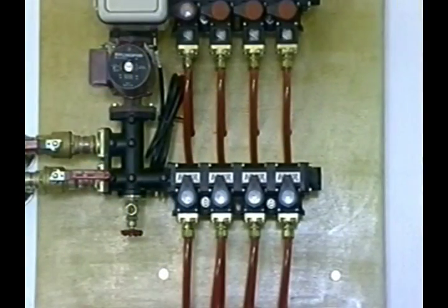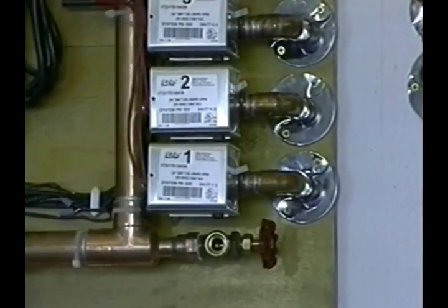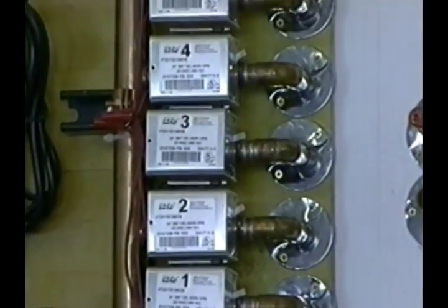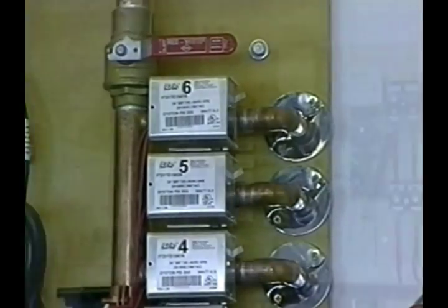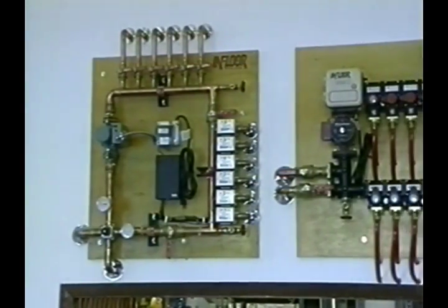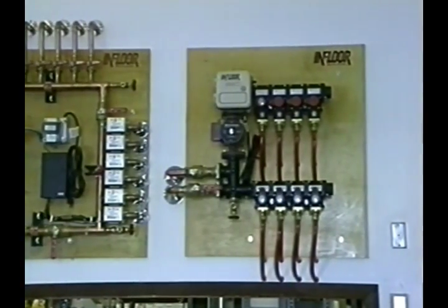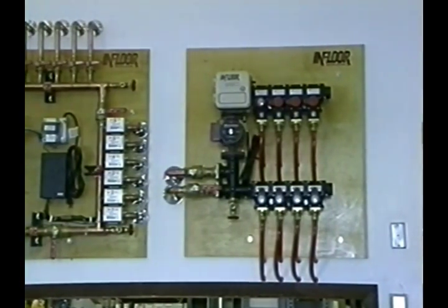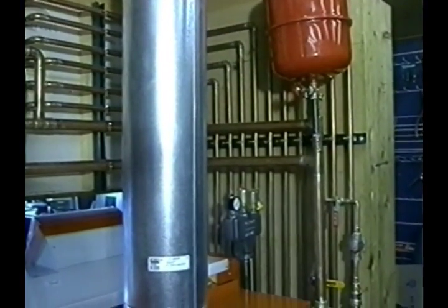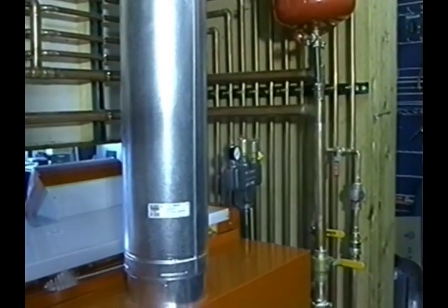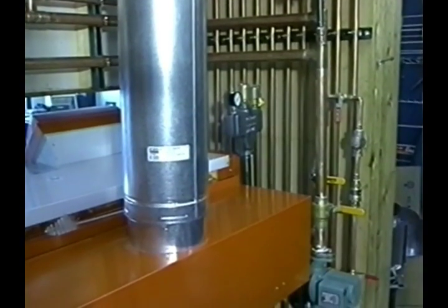Your supply piping goes to each remote manifold supply and returns from your remote manifold to the boiler room return. A zone valve is placed on the return side of your boiler room manifold. This, along with the thermostat, controls the temperature in each particular remote area. This process is continued until all remote manifolds are tied into the boiler room manifold. This completes the piping of your in-floor system. Some local inspectors require you to pressurize your system before filling it with water. It's also a good way to check for leaks.